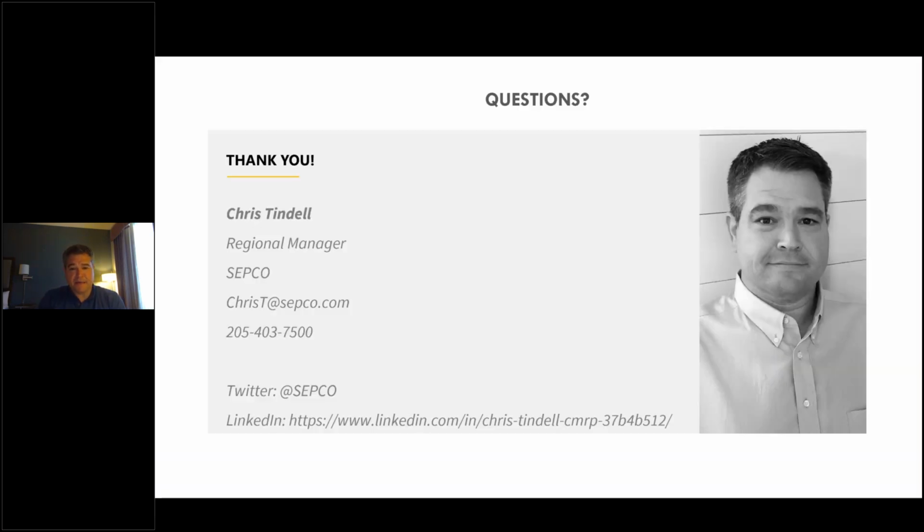That is the presentation. Again, I would suggest that to maximize pump reliability, mechanical seals must be treated as a rotating asset. There are so many benefits to doing that. It's easy to say, and it's not a complicated process, but anyone who has tracked motors or pumps as rotating assets understands that when a pump or a motor is rebuilt, it has to be serialized and then moved within your CMMS system. So there are extra steps, and it's something that people don't do lightly. We typically treat them as consumable items because we want to keep things simple.